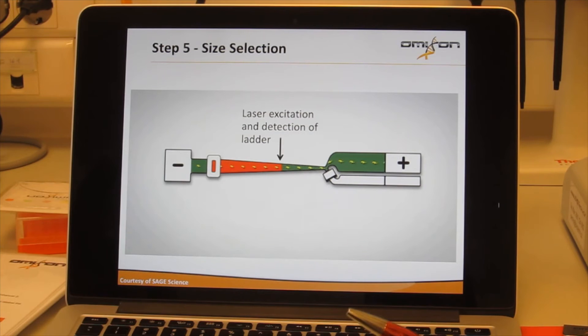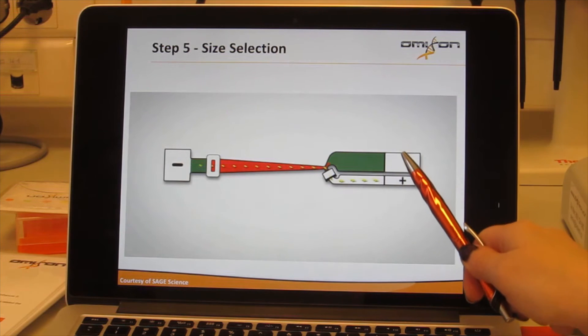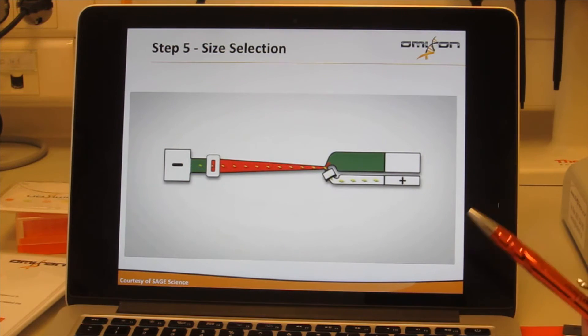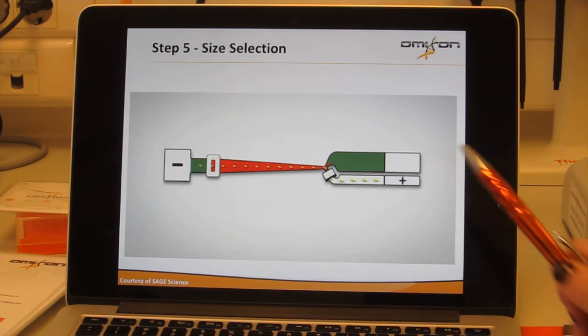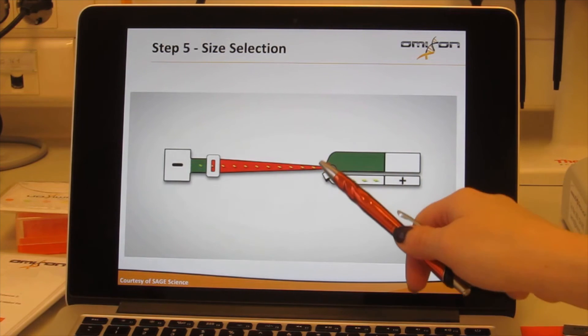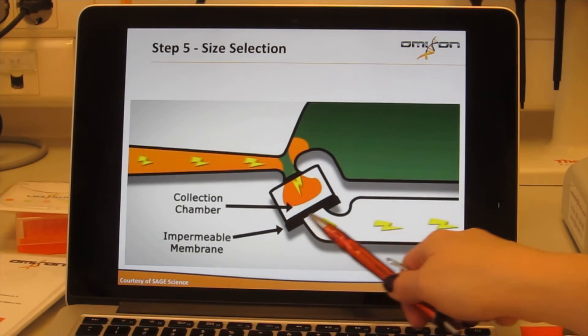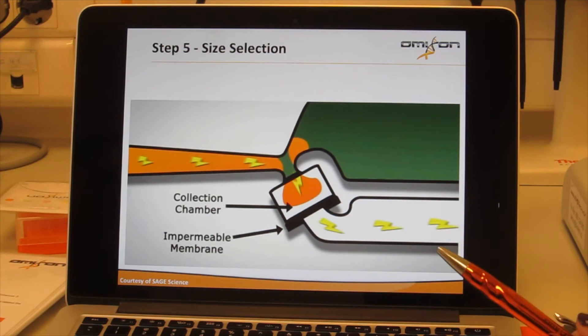Based on these two time points, the machine will calculate how much time a fragment size of 650 base pairs that we want to start collecting from will take to reach the same point. When the time has come, the positive electrode from one branch will be turned off and the positive electrode on the other branch will be turned on. As a result, the fragments that we want, instead of going into the agarose gel, will fall into the little collection chamber right here on the other side.